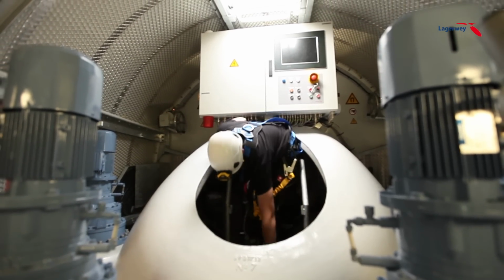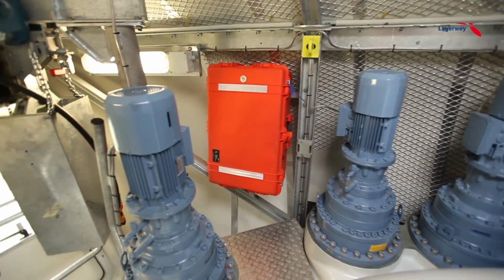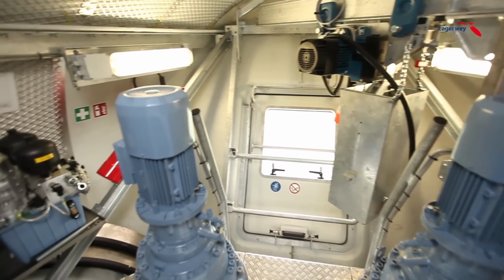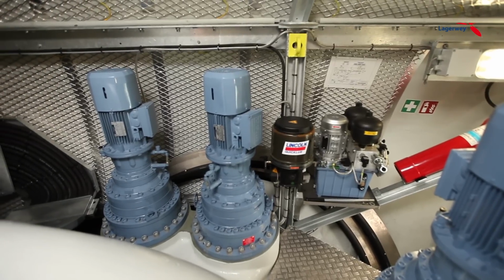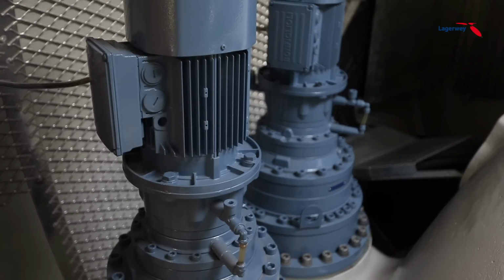The nacelle can be kept very compact thanks to the design of the direct drive generator. There is no big gearbox, complicated cooling system, or high voltage power transformer in this nacelle. Just 6 very reliable yaw motors which constantly turn the nacelle with its rotor facing the wind. These motors also deal with the great forces the rotor has to endure due to the turbulent wind.